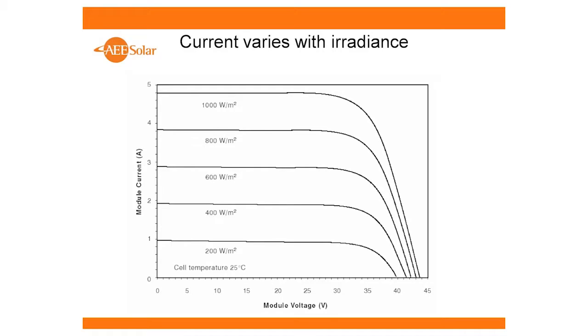But then we have to understand that our current varies, so this IV curve actually just slides up and down. It doesn't change shape, it actually slides up and down as we get more irradiance. More intensity of light, we double the intensity of light, we double the intensity of the current, and so this is the effect we see. Now we're going to see a little bit of a voltage difference here, but that's just because we're cutting off the IV curve a little bit differently as we go down in irradiance versus up in irradiance.